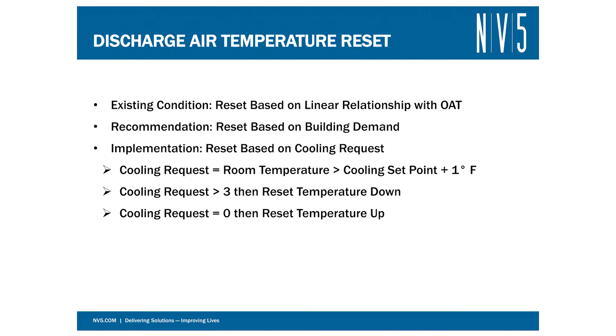Okay, so we're going to start with the discharge air temperature. We have two identical air handling units on opposite sides of the building, and they were resetting their discharge air temperature based on a linear relationship with outside air. We recommended a reset based on cooling demand, meaning if a space temperature was greater than its effective cooling set point plus 1 degree, that would send a cooling request to the air handler. If it accumulated 3, it would start to reset down, and if the spaces were satisfied and we had a total of 0 cooling requests, it would start to reset upwards. The building responded very well to this change.